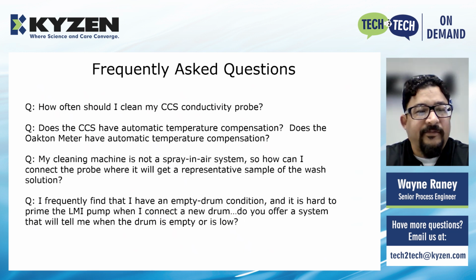Last question is, I frequently find that I have an empty drum condition, and it's hard to prime the LMI pump when I connect back to a new drum. Do you offer a system that will tell me when the drum is empty or low? Yes, here at Kyzen, we offer a couple different systems to measure the level in the drum. One is a manual drum level stick, and the other one provides a light tower and alarms when the drum is low or the drum is empty. You can contact us if you would like a quote for one of these systems.